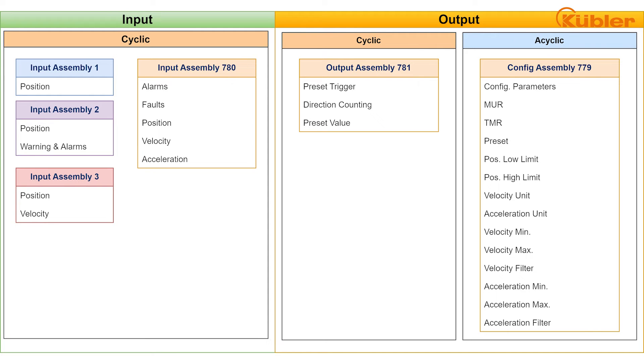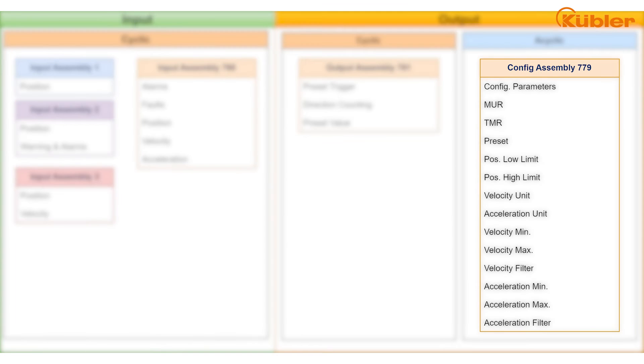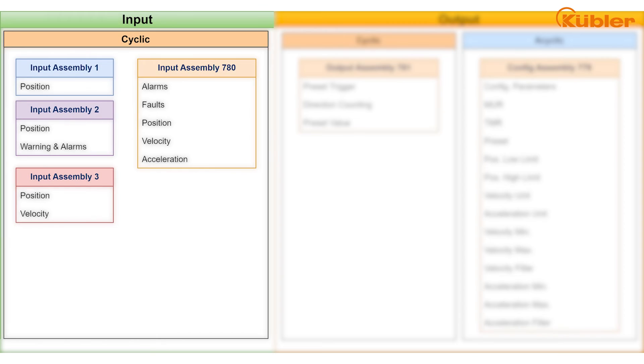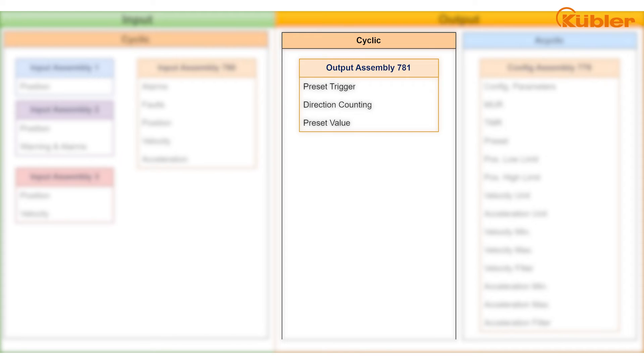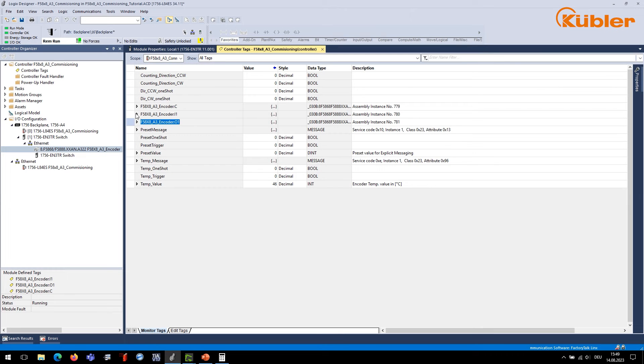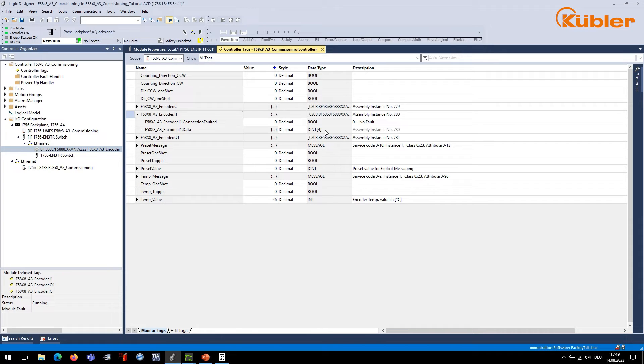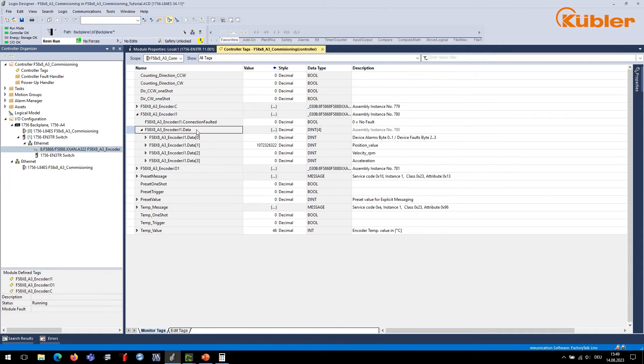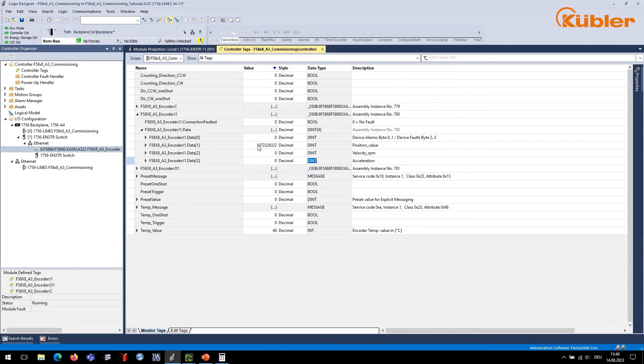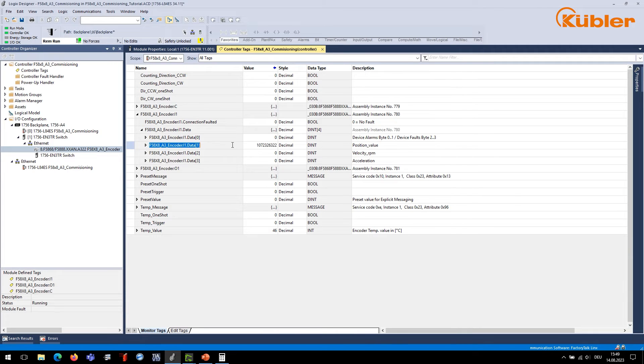Notice that the assemblies represent the three main categories of the encoder data: Configuration, Input data, and Output data. If you click on the assemblies, you can see that the input and output assemblies are arranged in the data format that has been chosen under Module Definition. Ideally, the data format corresponds with the length of each single attribute. In this case, double int is ideal. For demonstration purposes, we added a description to every attribute. If the shaft is rotated clockwise, we can see a change in the values position, velocity, and acceleration. This guarantees that the encoder was set up correctly and is working.